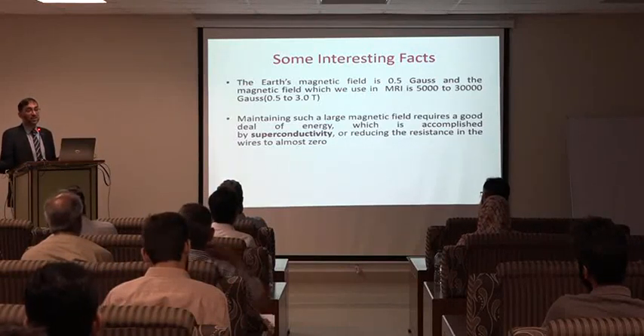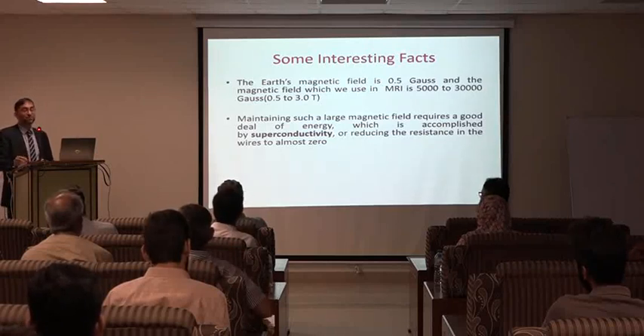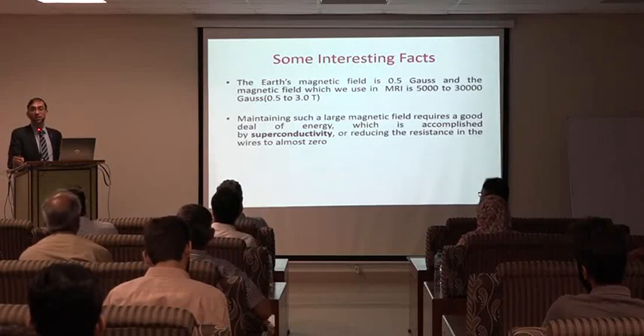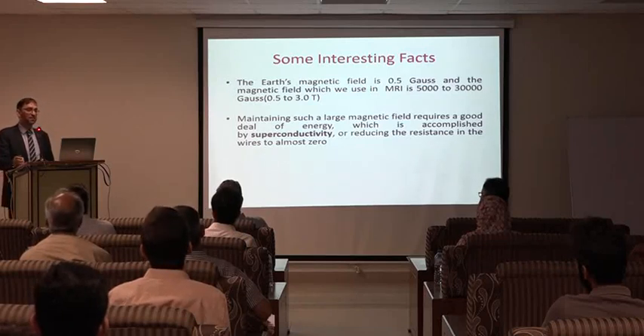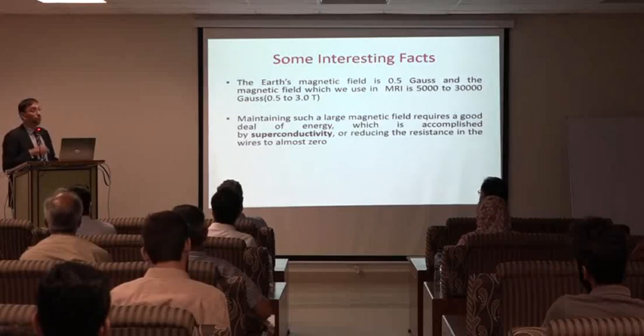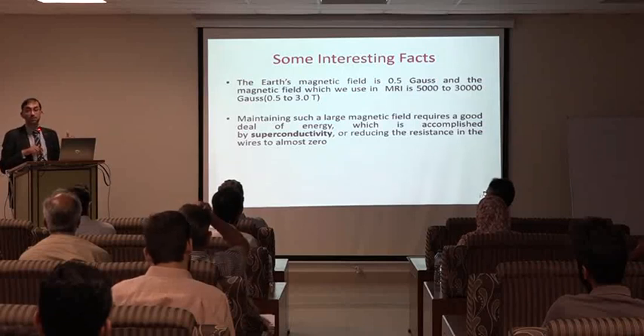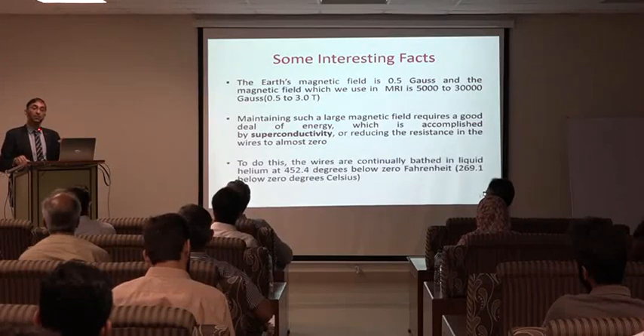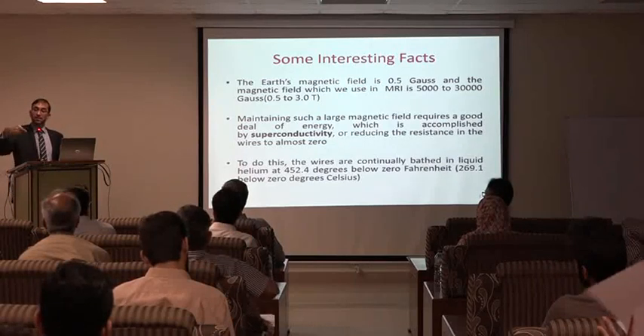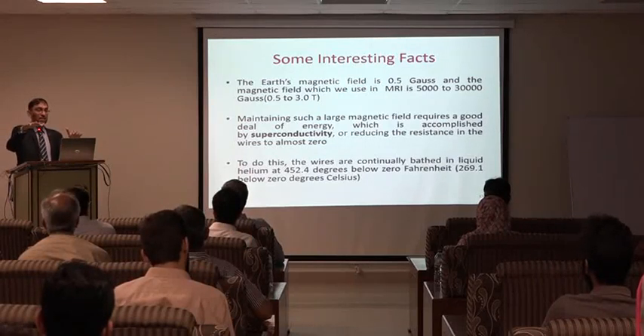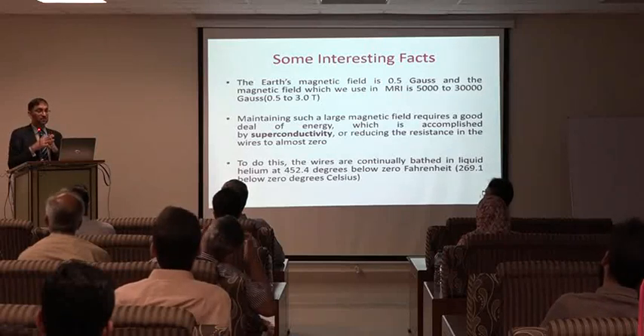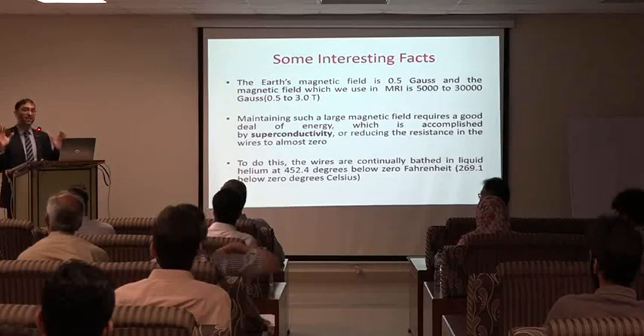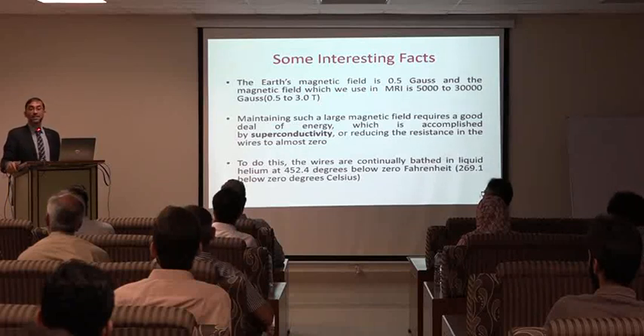Because otherwise, you imagine that 400 or 500 amps, the patient will just boil off. Because you can't operate the things at room temperature. You have to maintain superconductivity. Why? So that it reduces the resistance in the wires to almost zero. And by the way, the length of the wires which are around the scanner, in the scanner when the patient is lying, that goes a few kilometers. It's a very long length of copper wires there. All of them need to be properly bathed in helium.